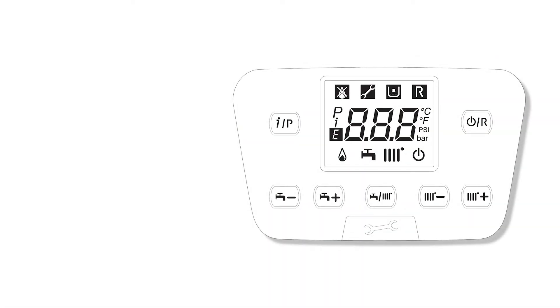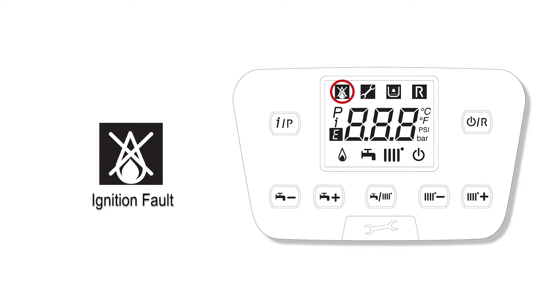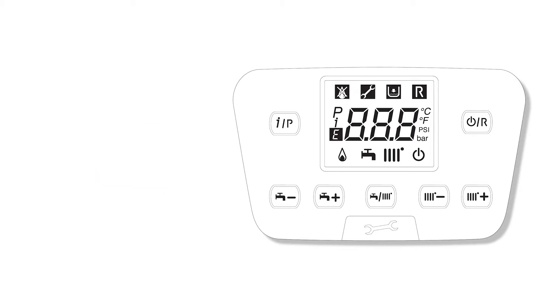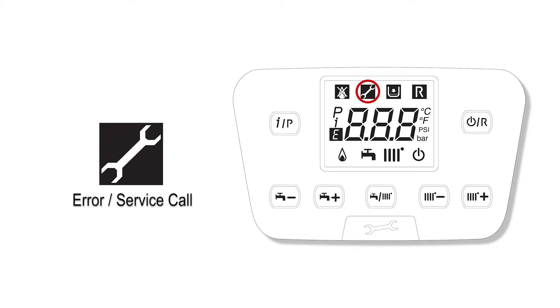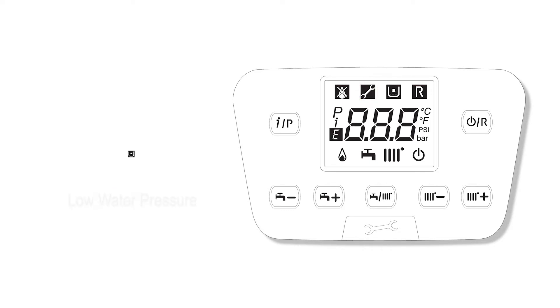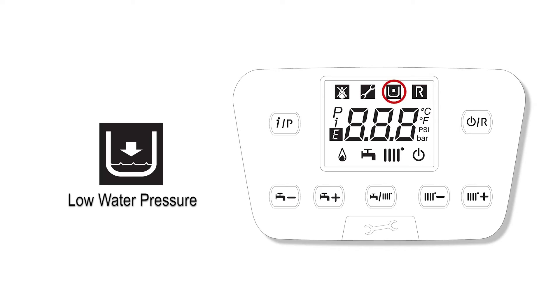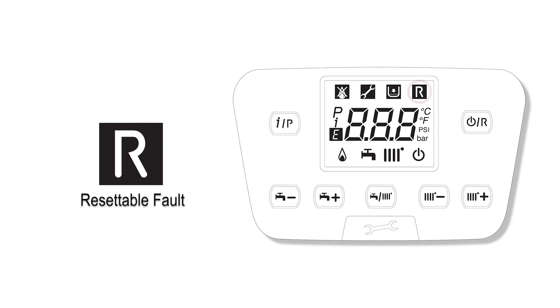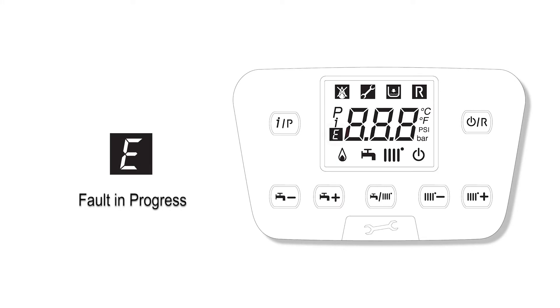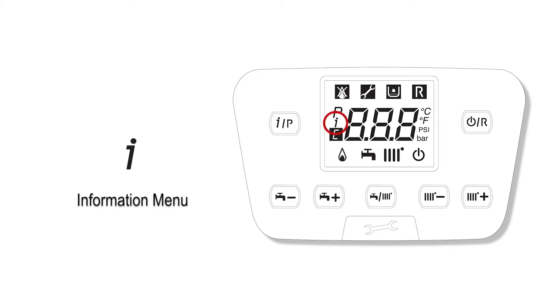Now we will look at the display itself. If there is an ignition fault, this icon will flash. A boiler fault requiring service will flash the wrench icon. If the boiler water pressure drops below 7.25 PSI, this icon will flash. The R icon is for a manually resettable fault. E is for a fault in progress. I is for the information menu. P is the programming or parameter menu.